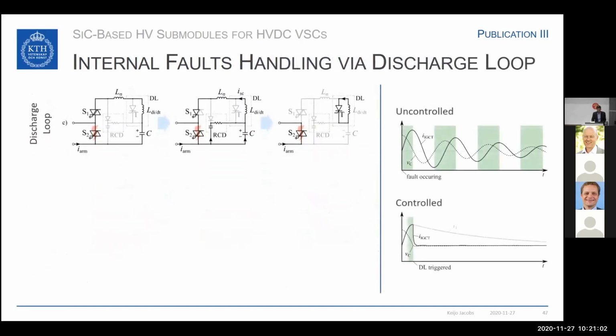I visualize this here in the uncontrolled and the controlled case. In the uncontrolled case, our capacitor discharges in a damped oscillation. You can see the voltage going down and oscillating. The current will go up, and the peak currents are normally in the range of several tens to several hundreds of kiloamps, which is very difficult to handle.